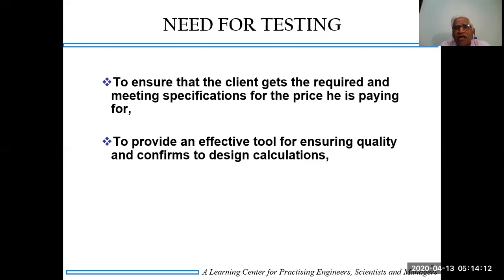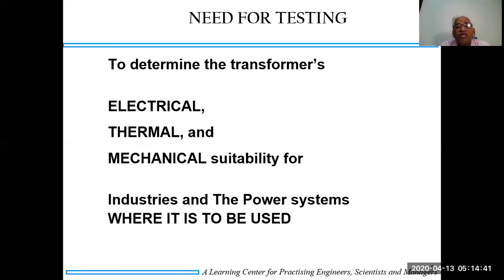And the client tells that I need an 11 kV transformer on the primary side, or 22 or 33, and on the secondary side he requires 433 volts mostly, 3-phase, 4-wire system, with the neutral brought out so that the neutral can be connected here. So they are all important things and one has to read them. Testing also provides an effective tool to ensure quality and conformity to the design calculations. This is also a very important need for testing.